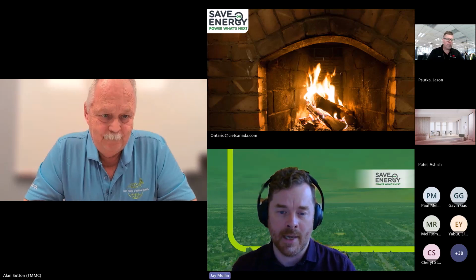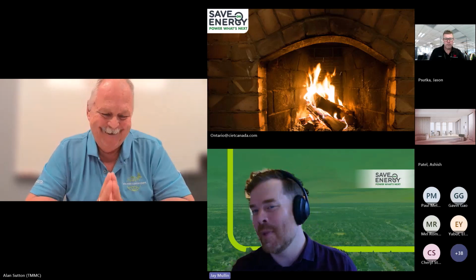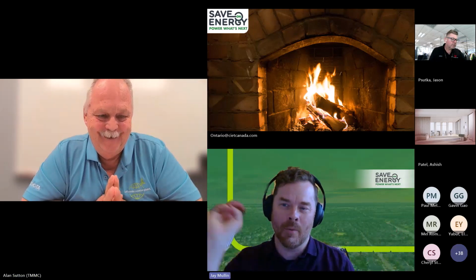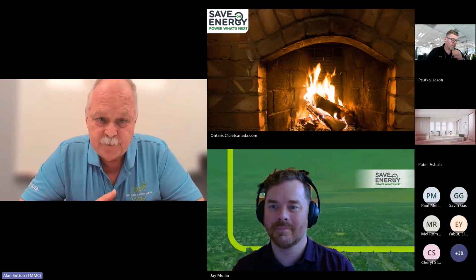There's a question about what other equipment uses VFDs at the plant, since it's a very massive facility. The highest number of VFDs are connected to HVAC equipment. Most of the other motors, like for chilling lines in the weld shop, are also on VFDs. Chilled water is probably the best example, but even water distribution throughout the plant is tied in with cooling towers that have VFDs on them. So it's quite widespread adoption of that technology, but a VFD is not good in every location.